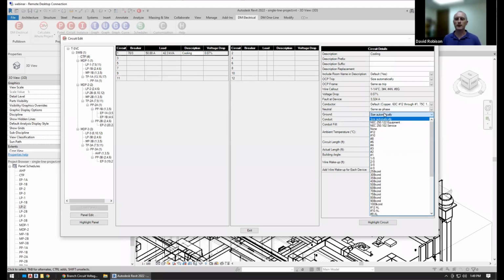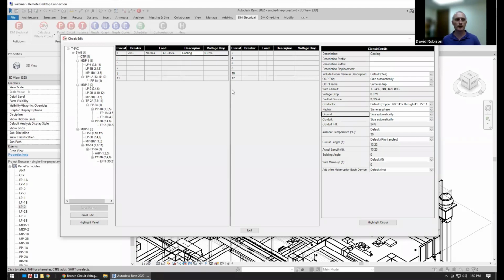We can specify the ground size automatically. It's going to size the ground based upon what it's connected to. For branch circuits, that's always going to be an equipment ground. If you connect to the utility or to a transformer, we put in a service ground. So the automatic size determines those two situations for you. You can force it to use an equipment ground or a service ground. So you can say, in this case it's generally going to be an equipment ground, but I want to size this one for a service ground for whatever purposes. It'll still size it automatically, just using the different NEC table, 250.102 versus 250.122. You also have the option to set it to none or a specific value if you need to. With ground sizing also, we will upsize the ground if you upsize your conductors for voltage drop.